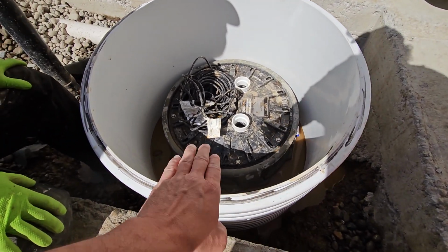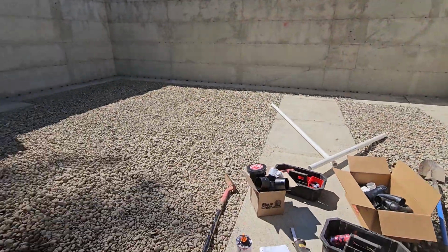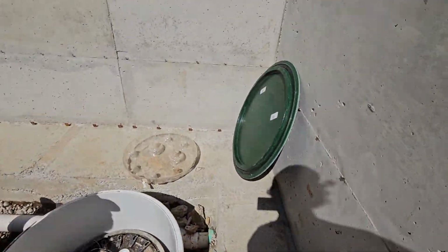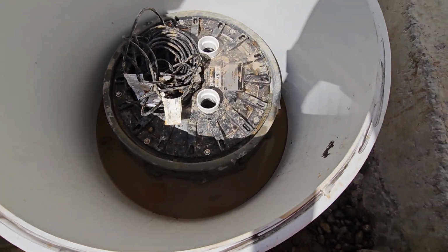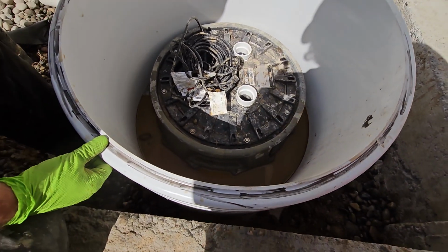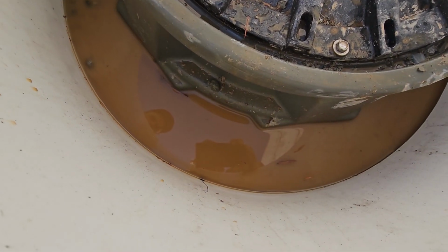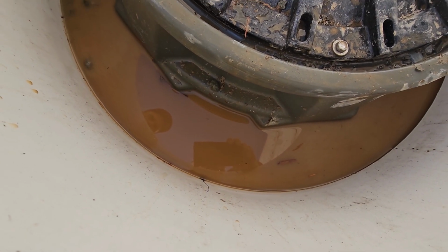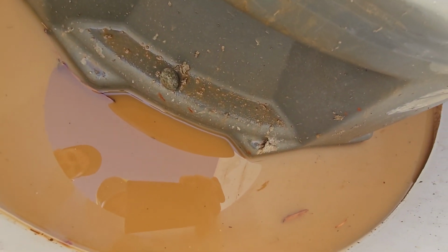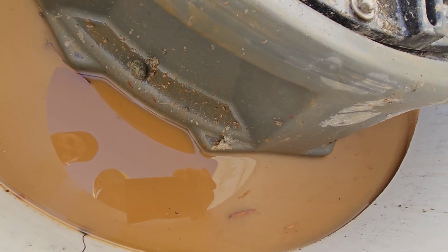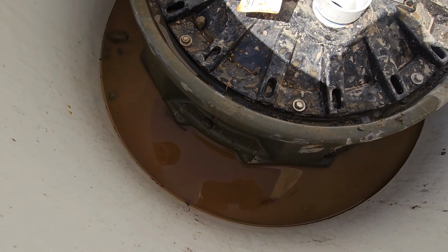We're going to put this septic tank riser around it, and when they go to pour this slab in here, we're going to ask them to pull that lid and pour concrete all the way around that tank. And under the water you can't tell, but there is a gap all the way to the bottom of this thing around it. So if they just fill this with concrete, the concrete will get underneath the lips of the body of this sewage ejector basin, and it'll lock it in.